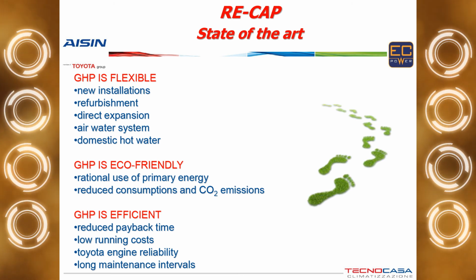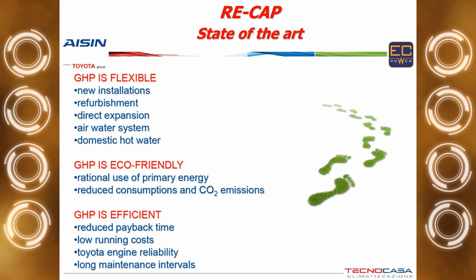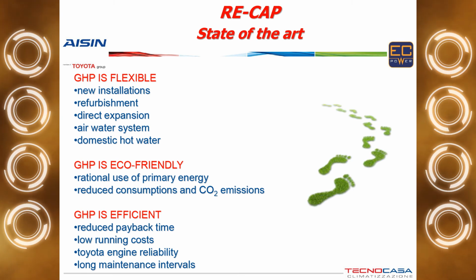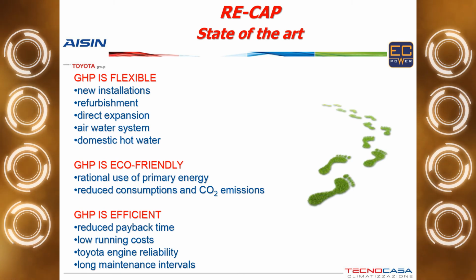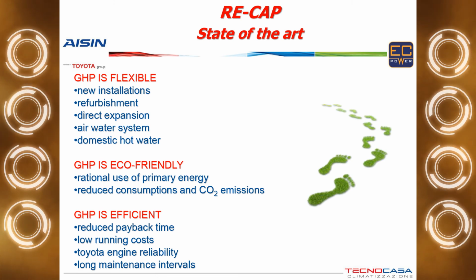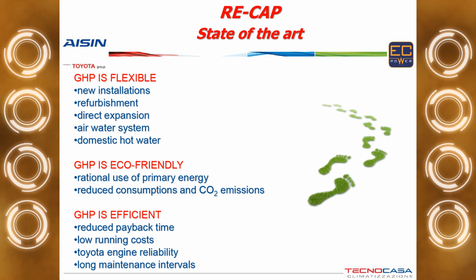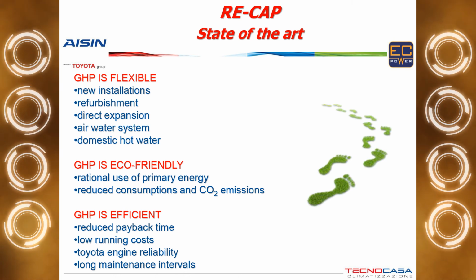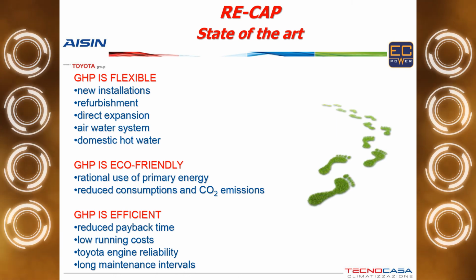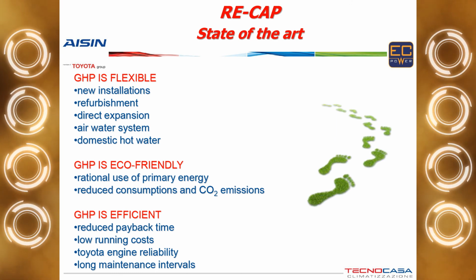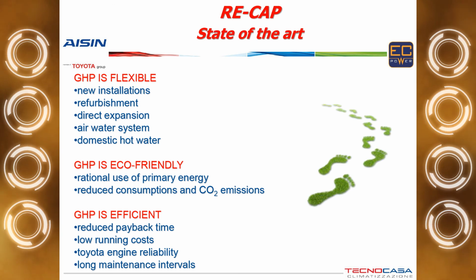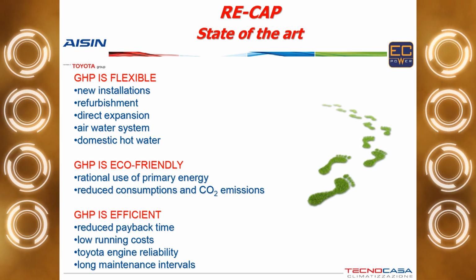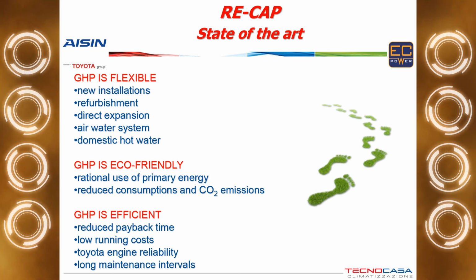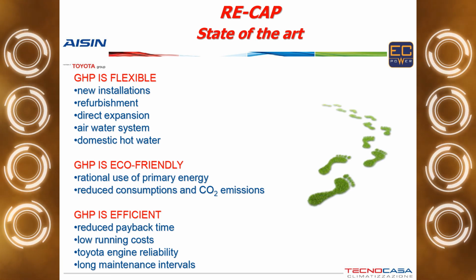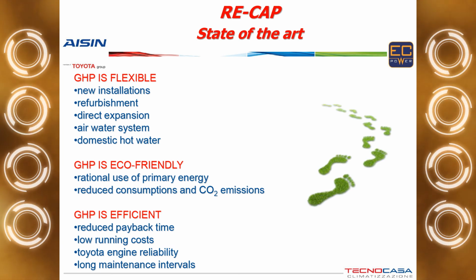The GHP is eco-friendly. There is a rational use of primary energy, and there are reduced consumption, and there is also reduced CO2 emission. So the carbon footprint of the GHP is reduced. The GHP is efficient because it has a reduced payback time, low running costs. This unit runs on Toyota engines, so those engines are quite reliable, and long maintenance intervals. You have to think that the manufacturer says the engine lasts 40,000 running hours. In our experience, we have some units which have reached more than 75,000 hours with no issues on the engines. So we know for sure that the engines are well designed and reliable.